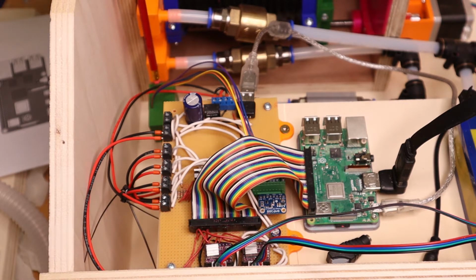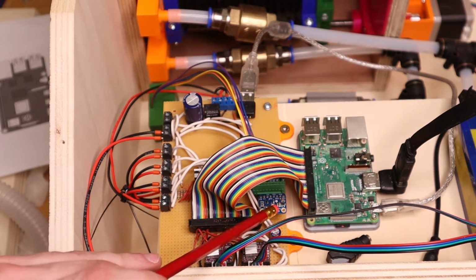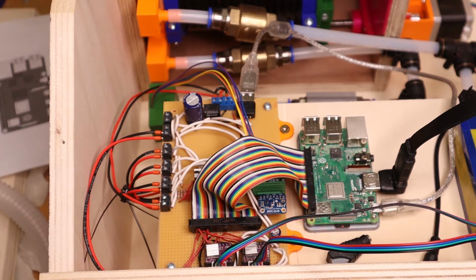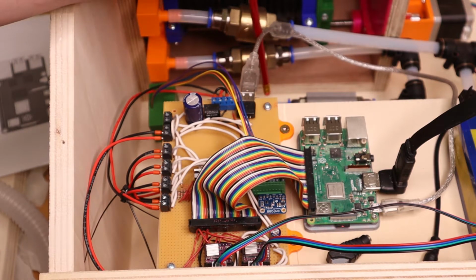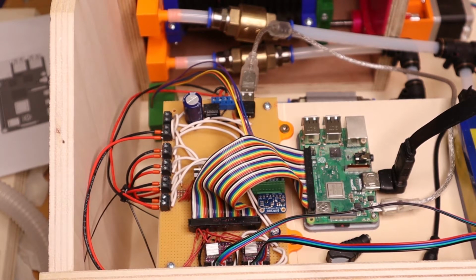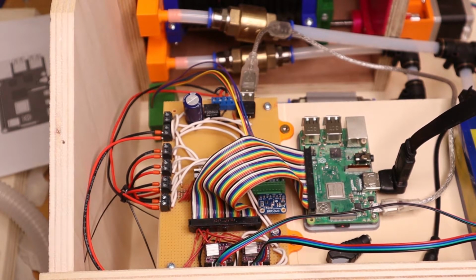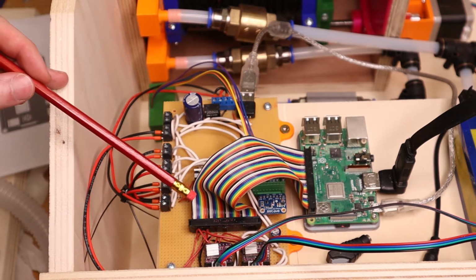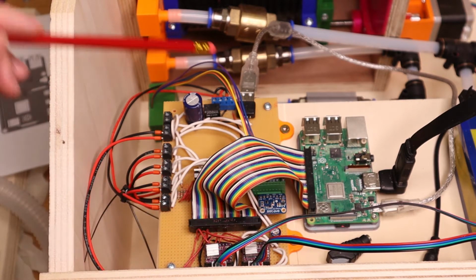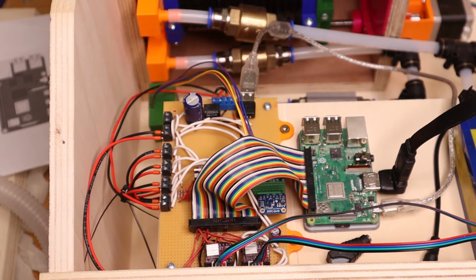And then there's a second BMP388 sensor in this box down here, which we've seen before. And so what the machine does is it measures the absolute pressure of the air just around itself and the absolute pressure of the air inside of the system. And the difference between those two is the gauge pressure, or the excess pressure in the patient's lungs. All of the pressures that you generally talk about when it comes to ventilation are gauge pressures. Now, I do think that it's more convenient to use one of the MPX pressure sensors rather than using a set of BMP388s. It doesn't matter so much accuracy-wise, but it is probably more convenient.